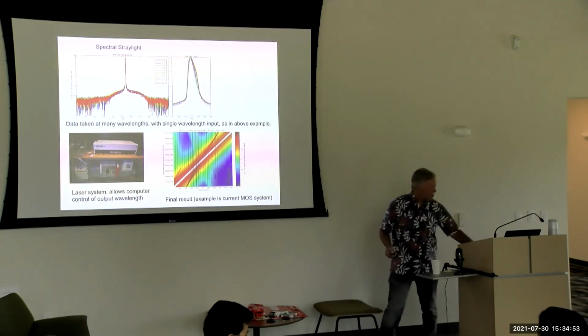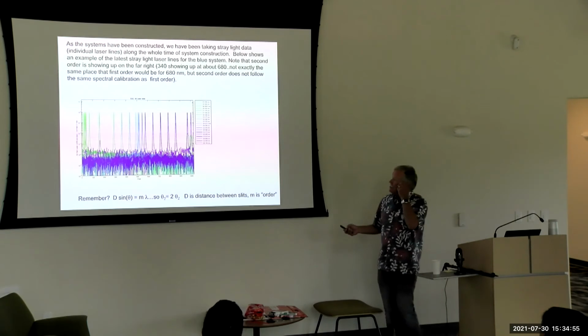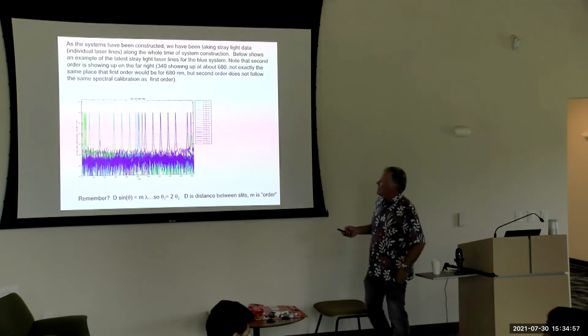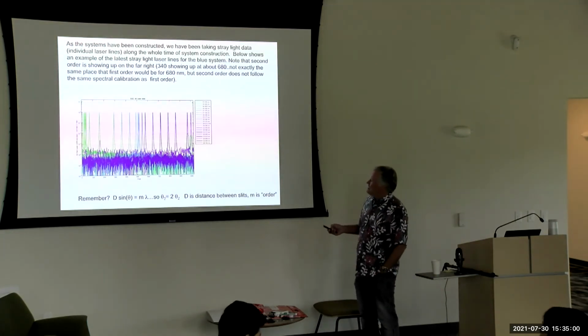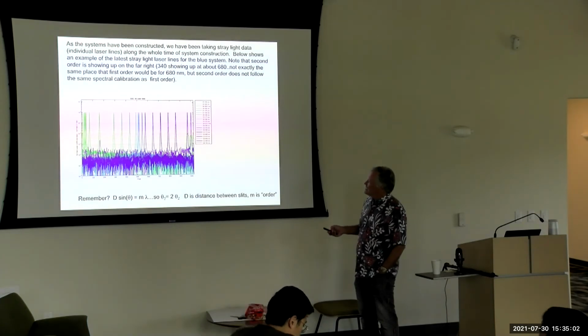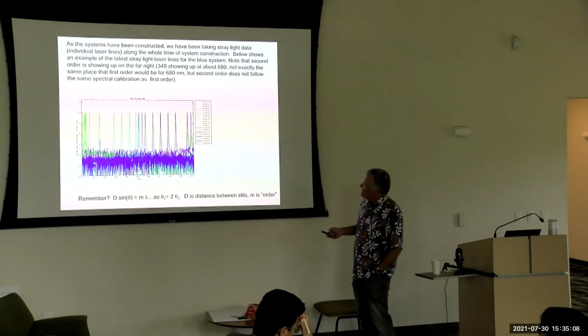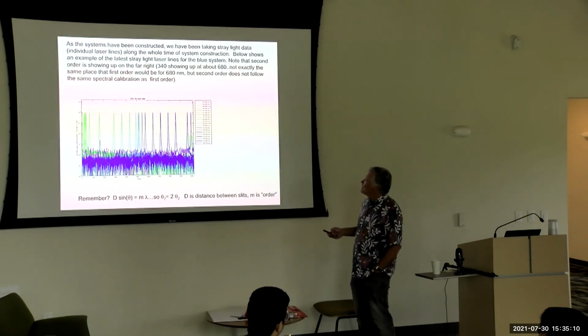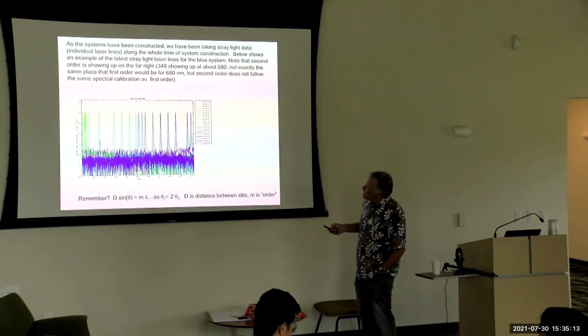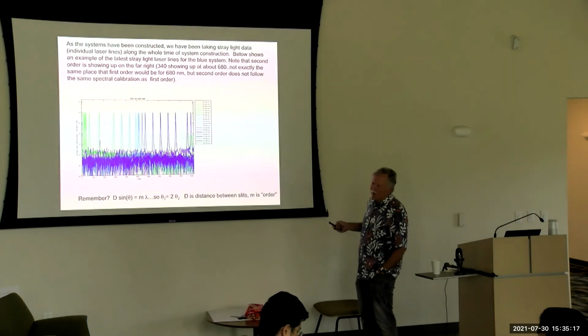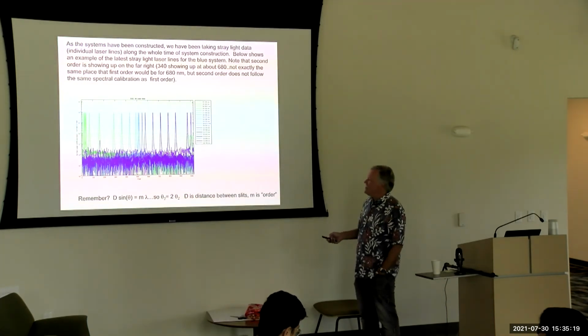But to do it, you need a whole bunch of stray light data. So this is the example of the blue spectrograph, with all sorts of different spectral lines, so we can characterize the stray light as a function across the array. Sort of interesting is we actually start a little bit below 350. So say 340 is showing up here, 340 nanometers. And you see it shows up over here too.